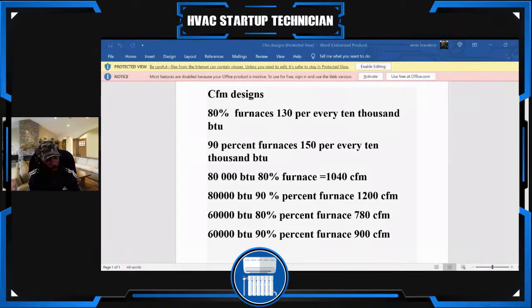You could just use your hand, pull these wires out, one out, and then put it back in, and you could say, okay, well, if I want medium, that's going to give me close to 1040. Sometimes it might not be exactly 1040. You might see 1060, 1050, but you get a picture that you're staying in the ballpark for what you need. So this is really, really important stuff. And again, I will repeat this, it doesn't matter the BTUs or anything. We're just working on the CFM part of it. Once we're talking about BTUs, we're actually going into gas pressure, which I hope to get to a little bit.